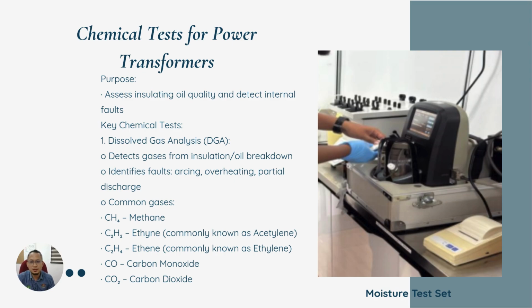Chemical tests like dissolved gas analysis (DGA) play a critical role in assessing transformer oil quality. DGA detects gases produced from insulation or oil breakdown, such as methane, acetylene, and ethylene, which can indicate faults like arcing and overheating. Other oil quality tests include measuring acidity, water content, and dielectric strength, all of which help assess the risk of insulation failure and oil contamination. Regular chemical testing ensures the transformer oil remains healthy and safe for use.